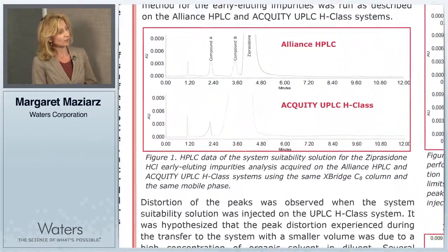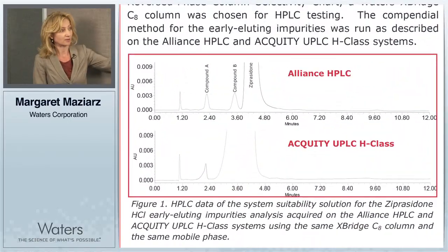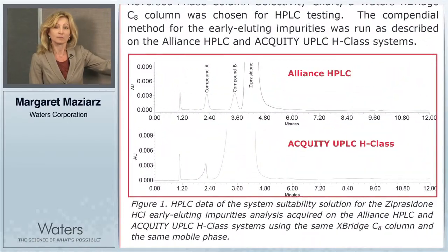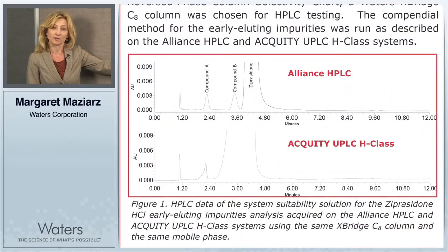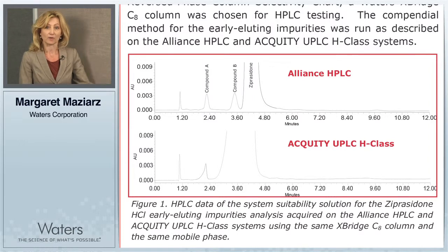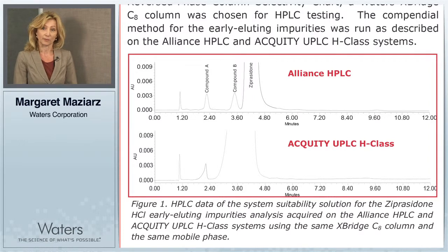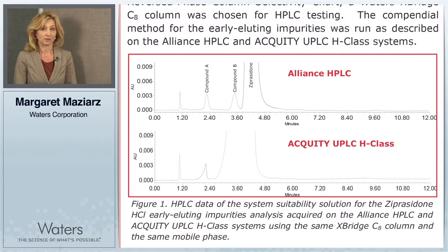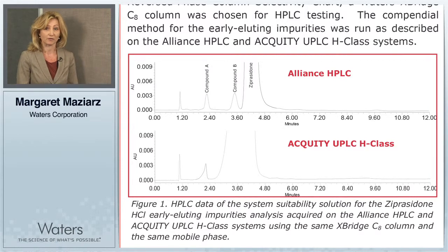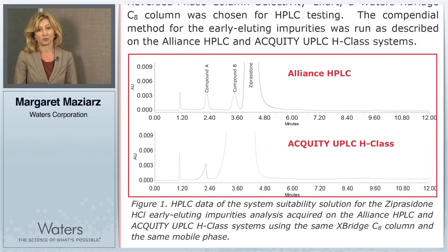While we transferred the method to the Acquity UPLC H-Class system, we found evidence of distortion of peaks. We designed several experimental tests to investigate and to solve the issue with peak distortion.